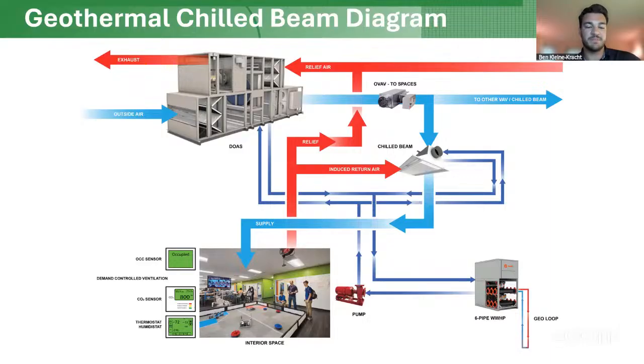Yeah, so here's the chilled beam design here. And I was going to mention that each one of these items on that matrix is just for the heating and the cooling. Each option has an additional DOAS that provides dedicated outside ventilation air to all of the spaces, and the air handling for the DOAS would be similar maintenance to any air handling unit you've ever seen - just fans and changing the filters and making sure the coils are not fouled up.